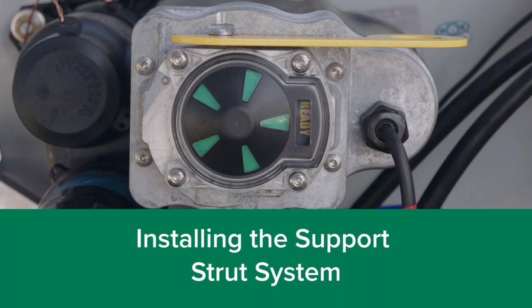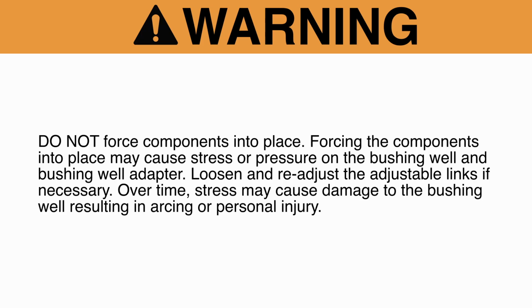Follow these steps to install the support strut system. Warning: do not force components into place. Forcing the components into place may cause stress or pressure on the bushing well and bushing well adapter. Loosen and readjust the adjustable links if necessary. Over time, stress may cause damage to the bushing well, resulting in arcing or personal injury.